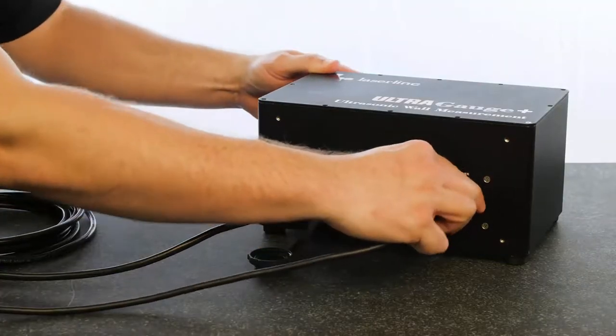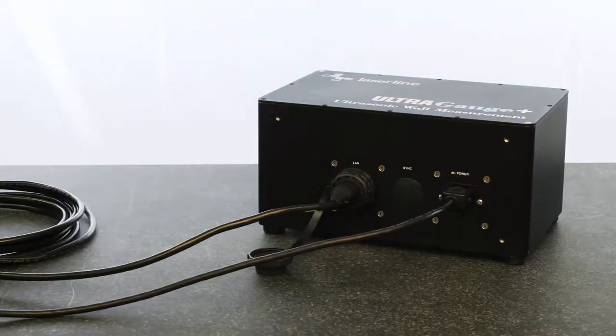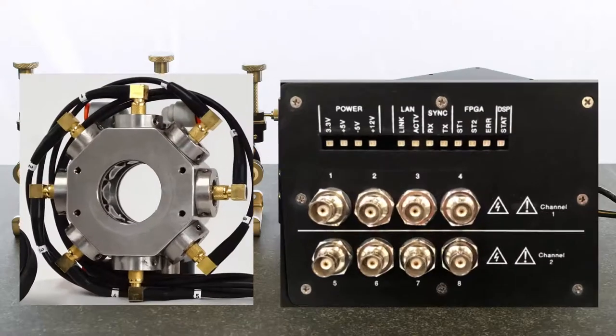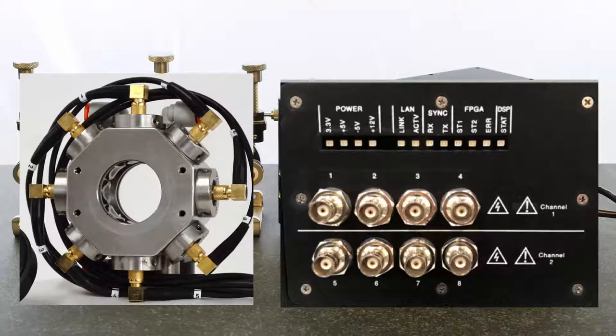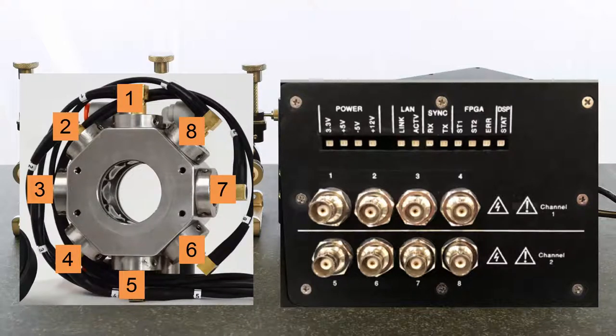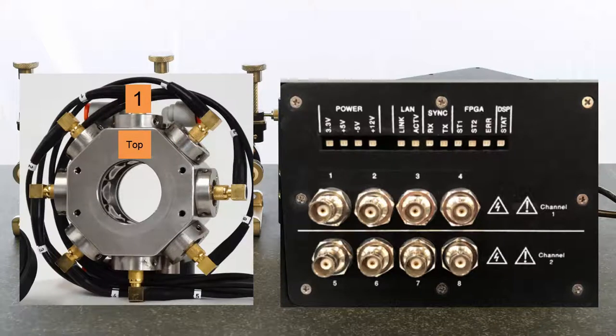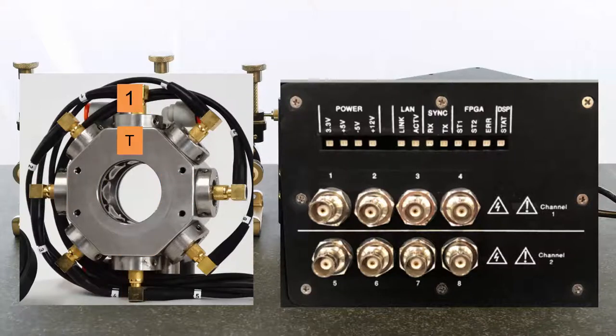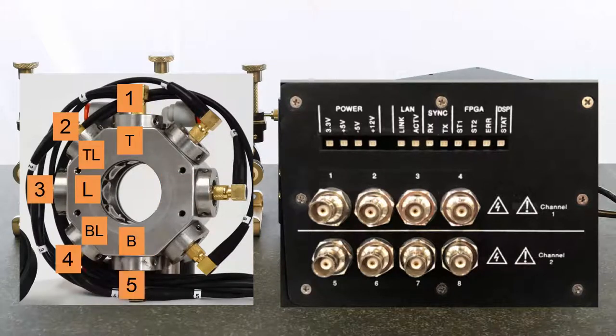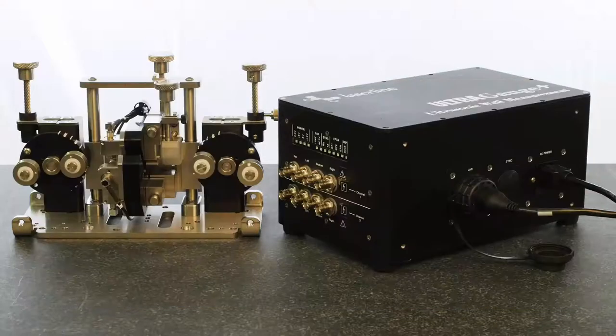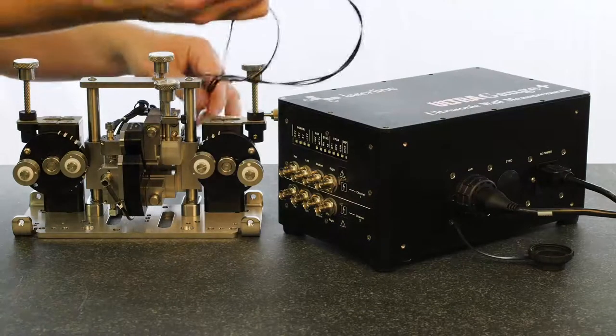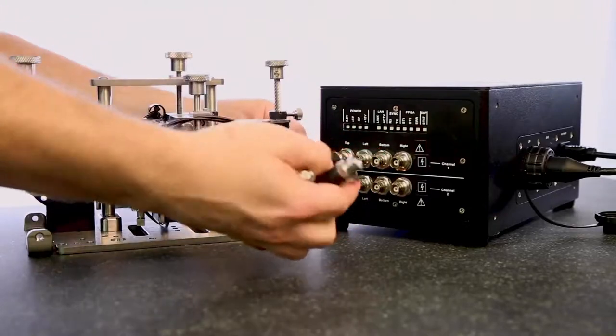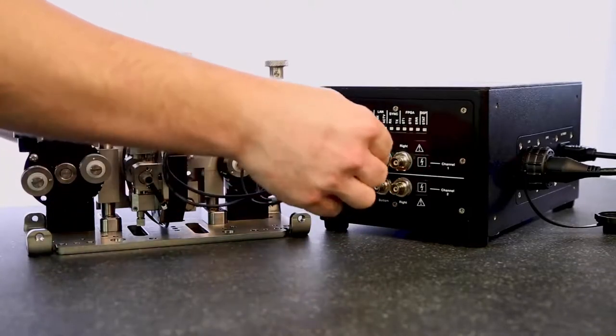Now we'll connect the sensor assembly to the DSP. The ultrasonic sensor assembly will have four or eight BNC cables already attached to the sensors. These cables should be labeled one through four or one through eight for eight sensor assemblies. These numbers correspond to the top, left, bottom, and right transducers respectively for a four sensor assembly or top, top left, left, bottom left, bottom, bottom right, right, top right in an eight sensor model. Plug each sensor cable into the DSP. Each end of the cable will be numbered with a corresponding value labeled in the appropriate position on the DSP.